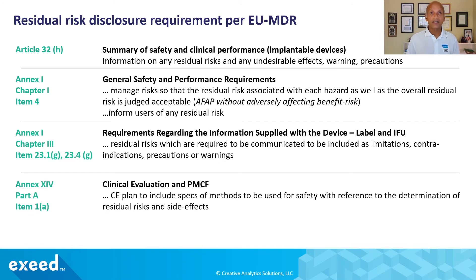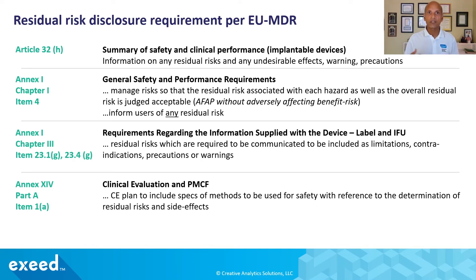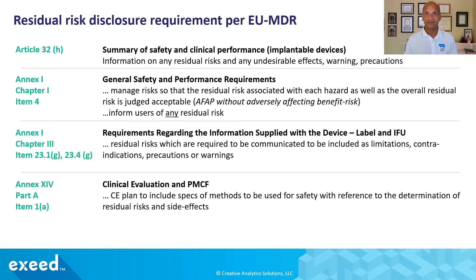Further, in Annex 14 on clinical evaluation and PMCF — post-market clinical follow-up — the clinical evaluation plan must include specifications of methods to be used for safety, with reference to the determination of residual risks and side effects. So they are requiring that as well.